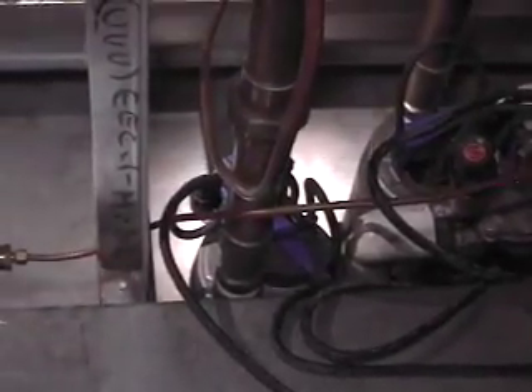Okay, so this is the direct evap section. So we've got several valves in here. Right here is your fill valve. So that will send water through the pipe here up into the sump sections here. And then inside the sump section, you've got your float valve right here, which controls the water. This is your actual fill valve right here. That's in series with our valve right down there. So when that fills up, it'll send pressure to this head and shut it off. Kind of a water actuated valve.